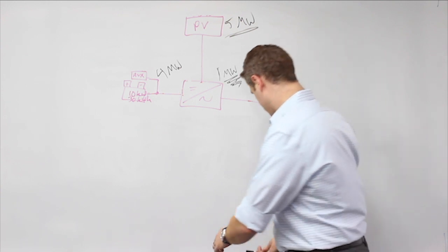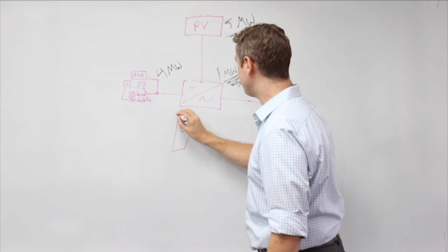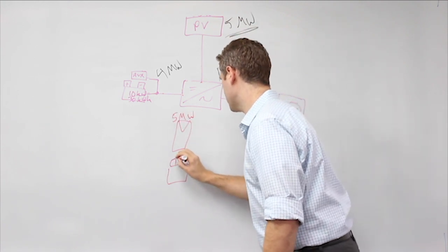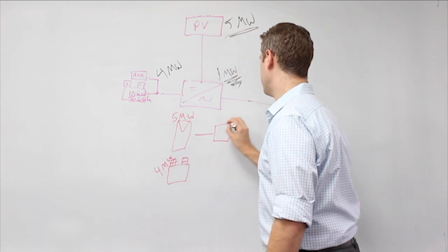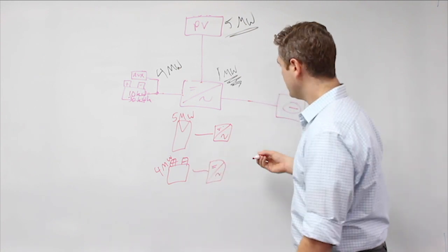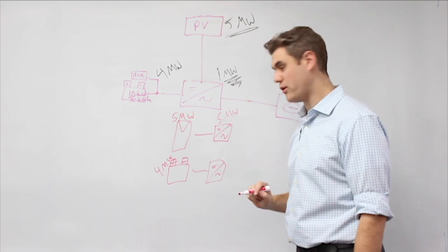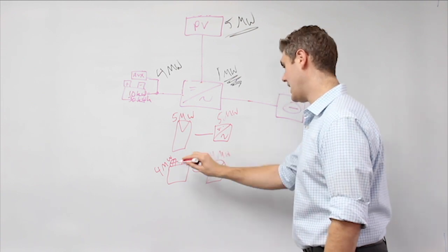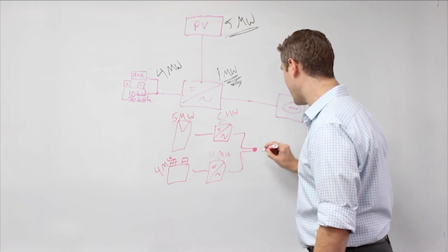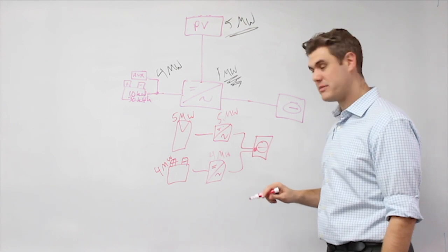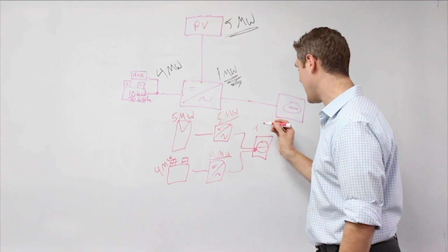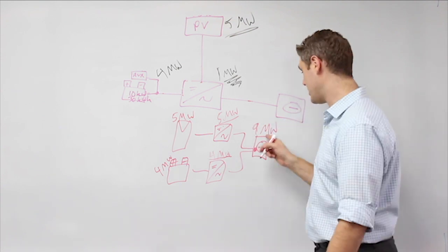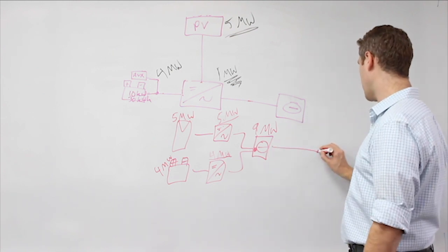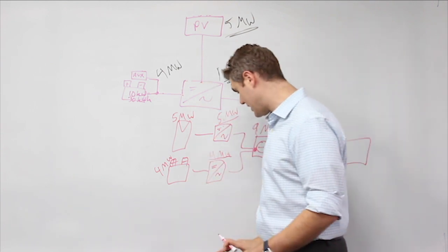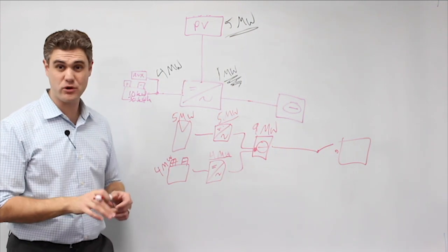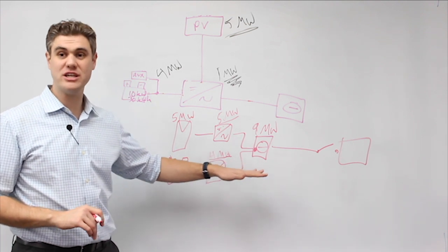So unlike an AC coupled system where you would have a solar panel, let's say you had 5 megawatts of solar and a 4 megawatt battery, and they both went through their own inverter. Well, this inverter obviously needs to be 5 megawatts to allow the full 5 of the solar through. And this certainly needs to be a 4 megawatt inverter to allow all the battery energy in and out. And then if these guys connect together on the AC side at the utility, well, the interconnection department says, this is a 5 megawatt system, this is a 4 megawatt system. You could potentially export up to 9 megawatts into my grid. And that's a lot of power I got to manage. I got to make sure the feeders are big enough, the reclosers are big enough, and the substation 5 miles down the road is big enough. And oh, by the way, you're responsible for all those interconnection costs and upgrade. So AC coupled is actually really challenging to interconnect from that perspective.